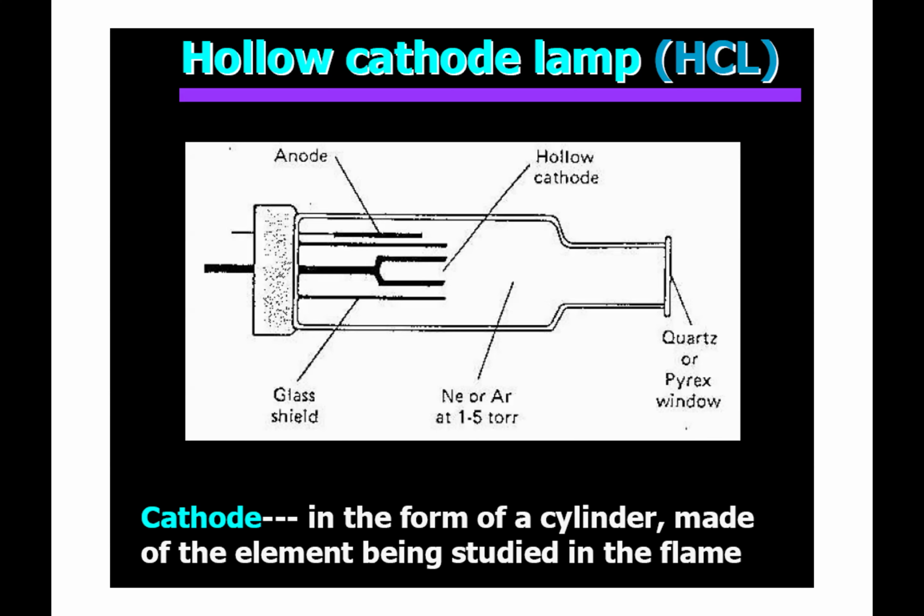So look at this. What do you see? This is how a hollow cathode lamp works. You want to see the voltage, right? Do you see where the voltage is? You have the leads on it. On this end here, you have where you plug it to the socket. And then you have the terminals there. And then you notice you have the anode and the cathode. And we have something there that is like a tuning fork, and that is the hollow cathode. The hollow cathode looks like a tuning fork when you look at it. And we'll see how that is fabricated.